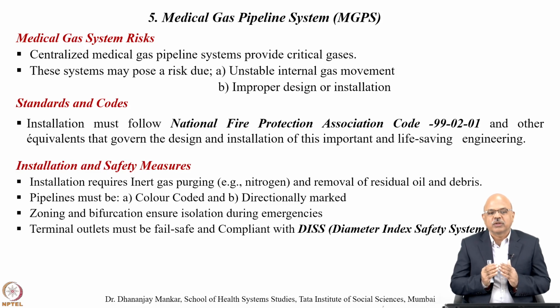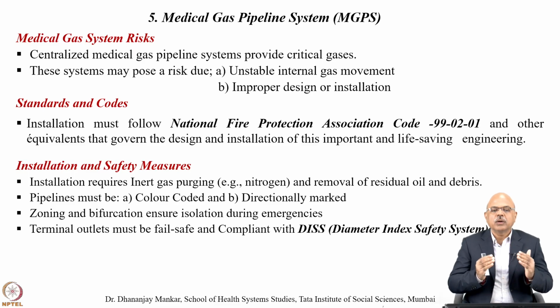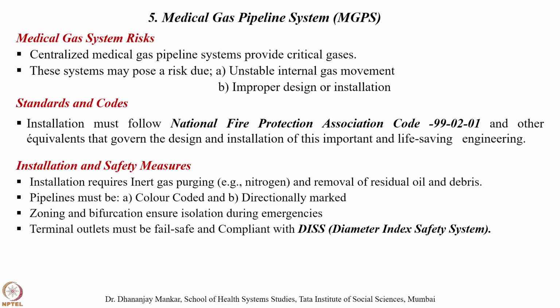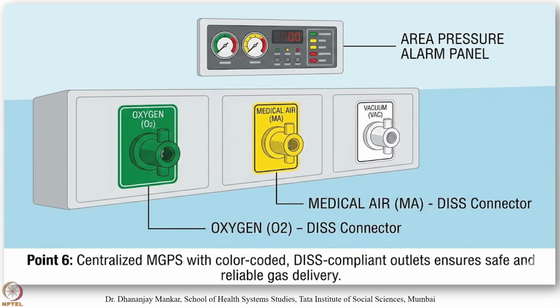Installation and safety measures. Installation requires inert gas purging, that is nitrogen, and removal of residual oil and debris. Pipelines must be color coded and directionally marked. Zoning and bifurcation ensure isolation during emergencies. Terminal outlets must fail safe and be compliant with DISS, that is the diameter index safety system, which emphasizes how this medical gas pipeline system, if installed, needs to handle the critical part.